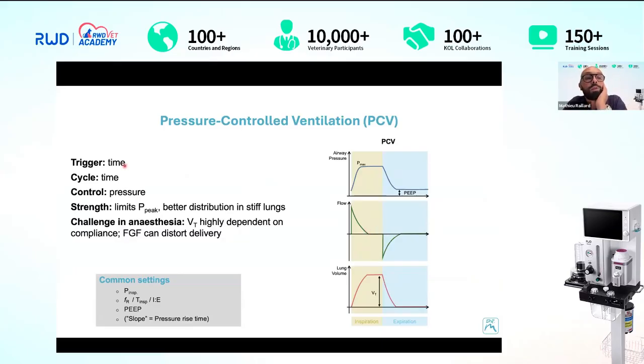What do I set when I set the pressure control ventilation? Well, trigger and cycle are going to be the time. So I set the respiratory rate and either the inspiratory time or the ratio of the duration between inspiration and expiration, and I set my pressure.